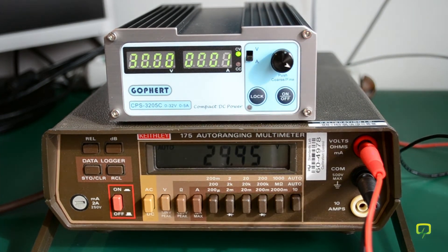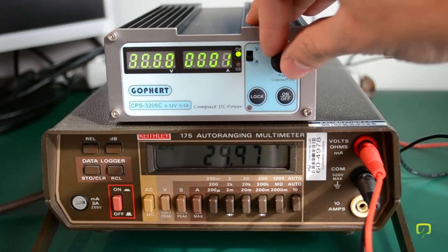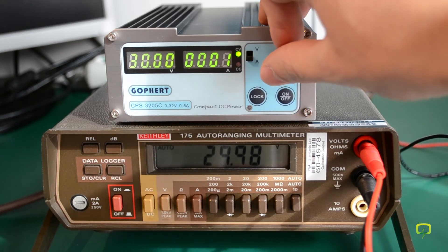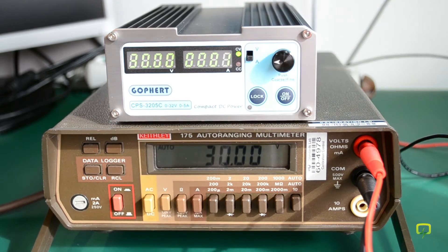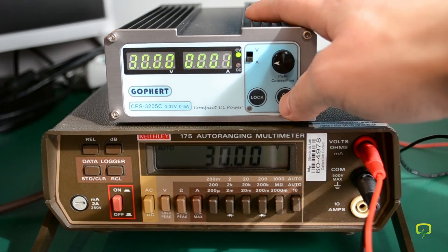And it jumps to the 30 volt mark. Once again, you adjust it so we get 30.00 volts. And now if you press the on/off button again, it will go into current calibration mode.